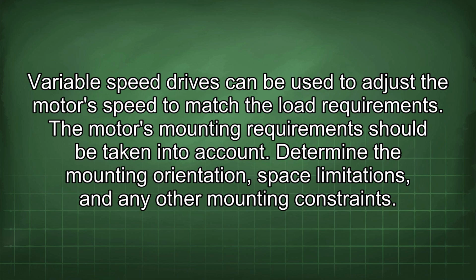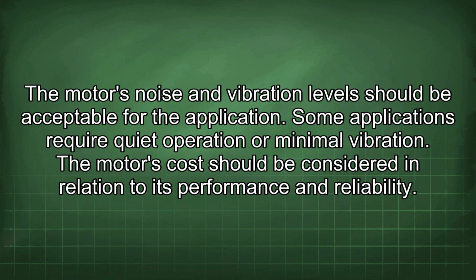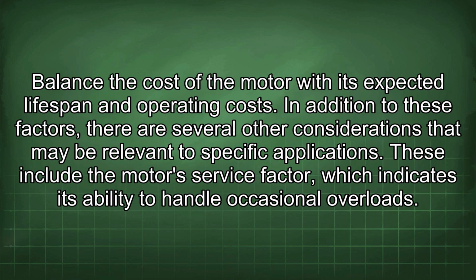The motor's mounting requirements should be taken into account. Determine the mounting orientation, space limitations, and any other mounting constraints. The motor's noise and vibration levels should be acceptable for the application. Some applications require quiet operation or minimal vibration. The motor's cost should be considered in relation to its performance and reliability. Balance the cost of the motor with its expected lifespan and operating costs.